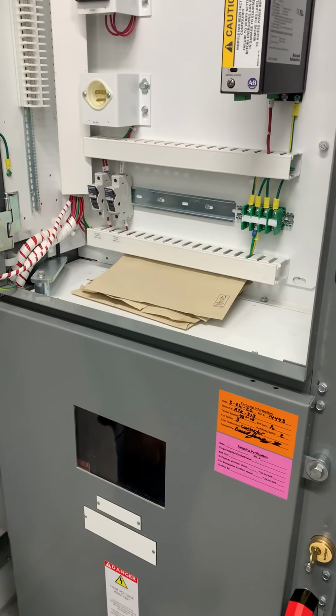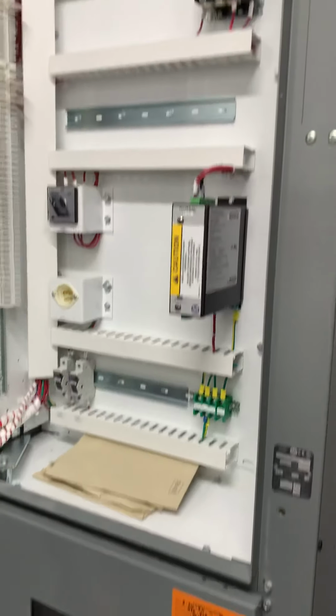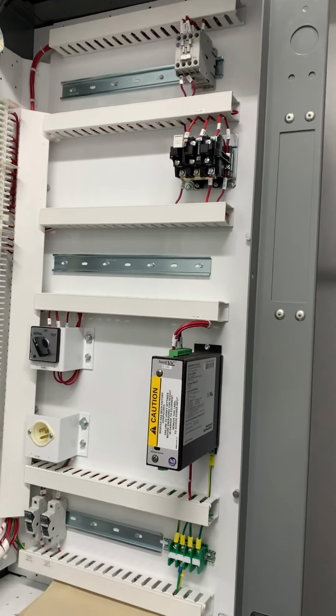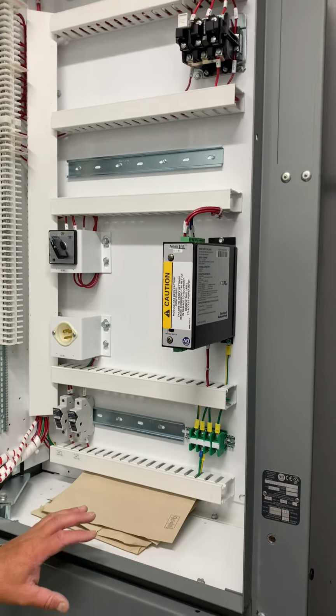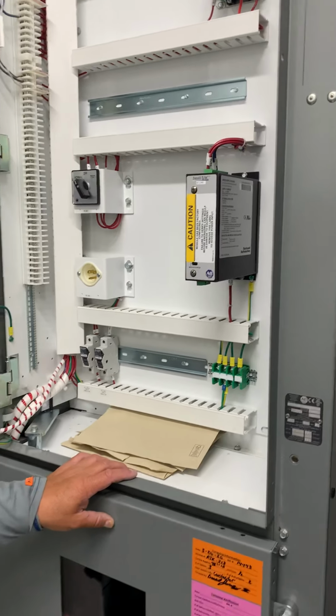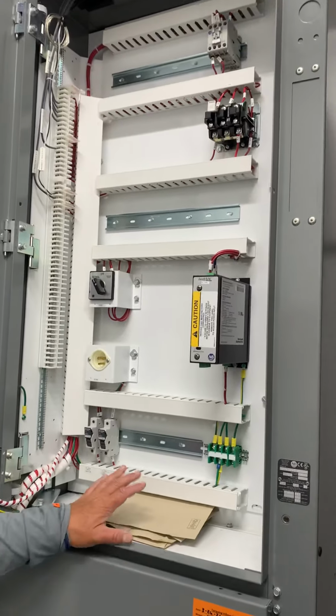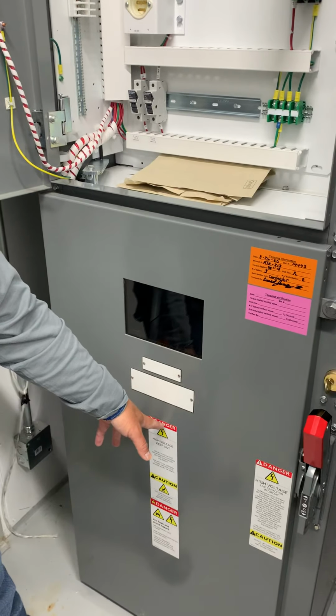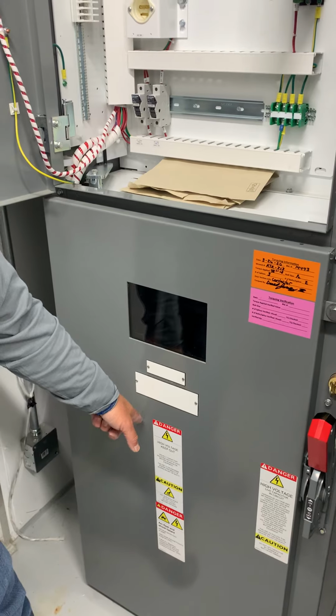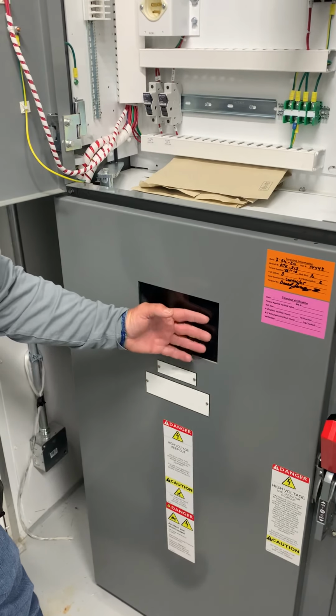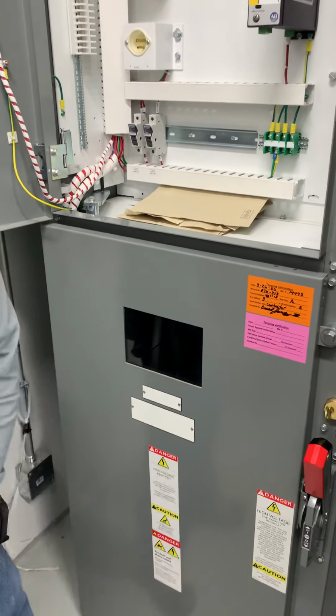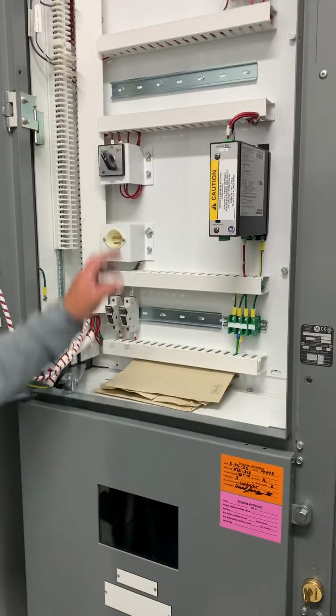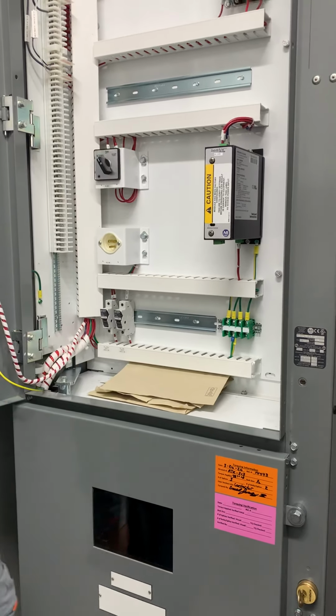That's what we did the very first thing. So that's your test mode, and what that does is give remote power to this so it'll operate correctly, so you can test everything. This power normally comes from two fuses on top of that vacuum contactor, and there's a transformer back there that supplies the control power for this when the medium voltage is on. So as long as that's in normal, you should be good.